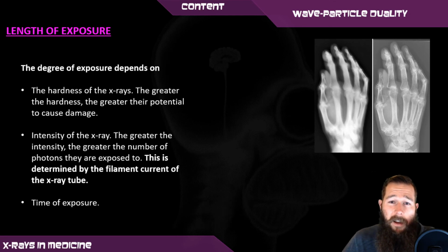As X-rays have high energies and can pass through our skin, it's important to minimize the time of exposure for safety reasons, but also control the hardness of the X-ray appropriate to the application. So to produce the best image, the hardness of the X-rays needs to be chosen, the intensity of the X-rays, followed by the time of exposure.